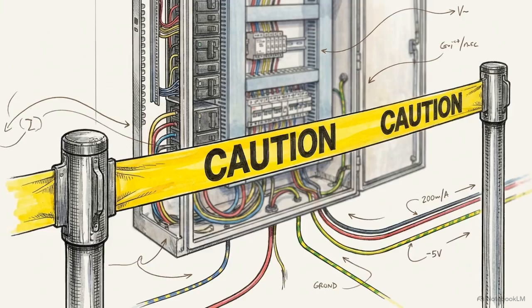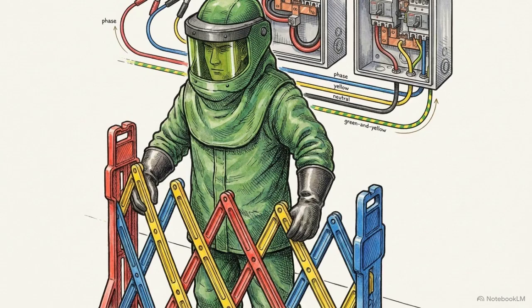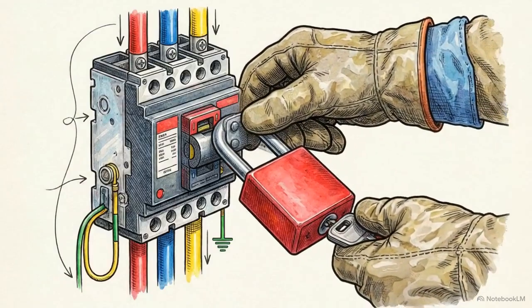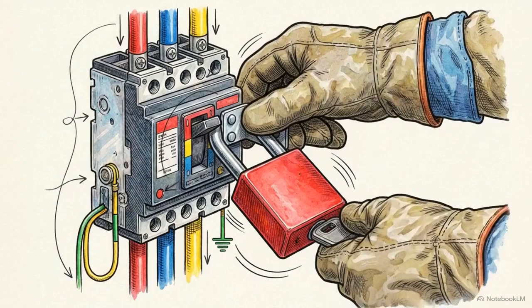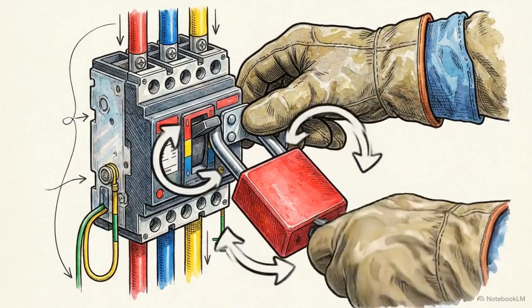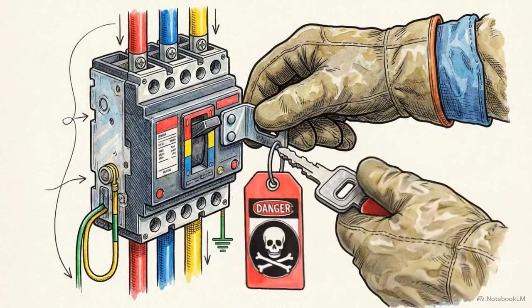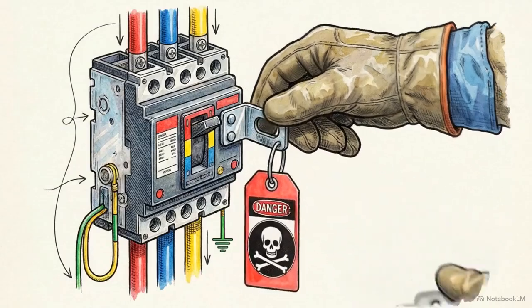Before connecting a single test lead, engineers must establish a secure physical boundary. This requires verified safe isolation, installing physical safety barricades, and wearing appropriate personal protective equipment. The area must undergo a strict lockout and tagout process. Engineers physically lock the energy sources and actively verify the complete absence of voltage.